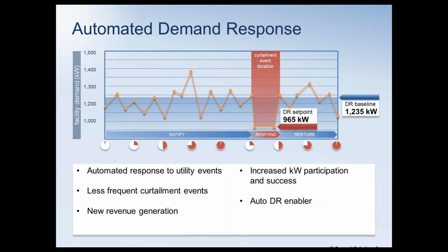The automated demand response that we signed up for originally required us to manually go out and adjust and set down the set points. With the Power It system, we were able to dial in to the system, and I would always receive the notice for the brownout conditions, and I would have to call the plant and get the furnace operators to turn down their power. With the automated demand response, we were able to install a phone switch so that once I received notification from the utility that we had to go into an event, I could dial in and automatically set the automatic system from our 4,500 kW on-peak demand set point. We could automatically set it down to, in our case, 2,500.